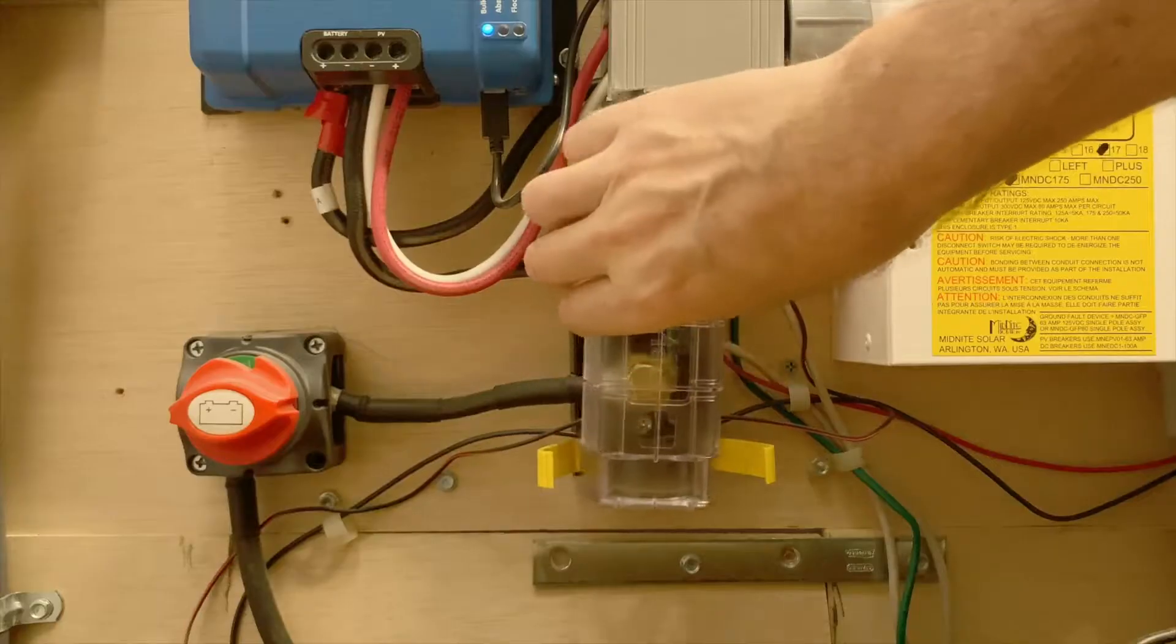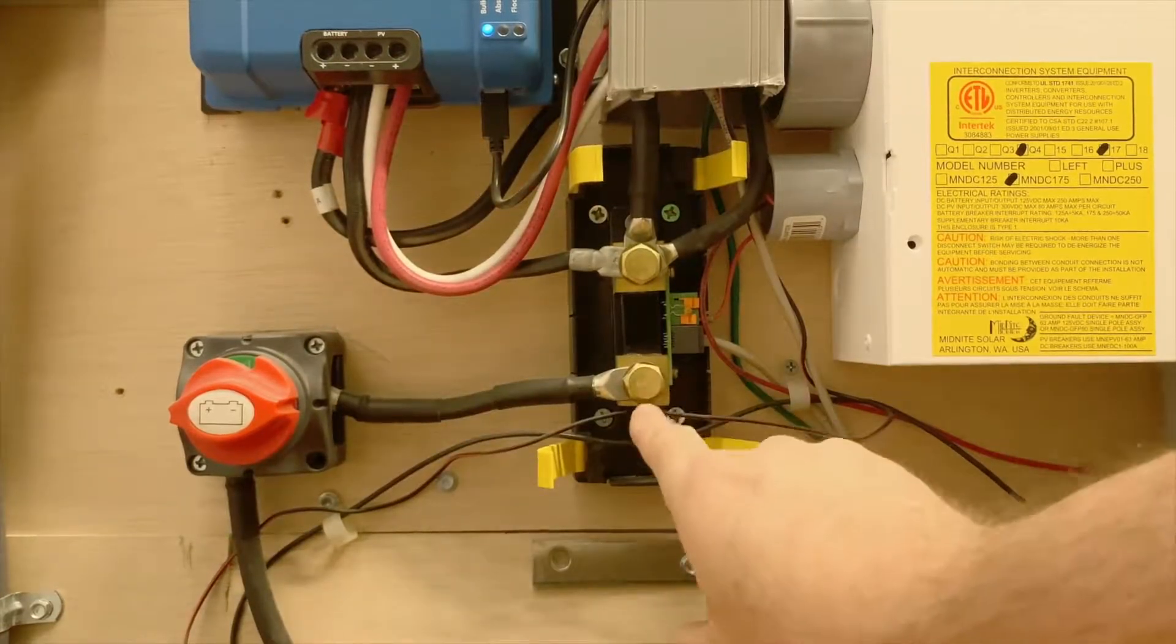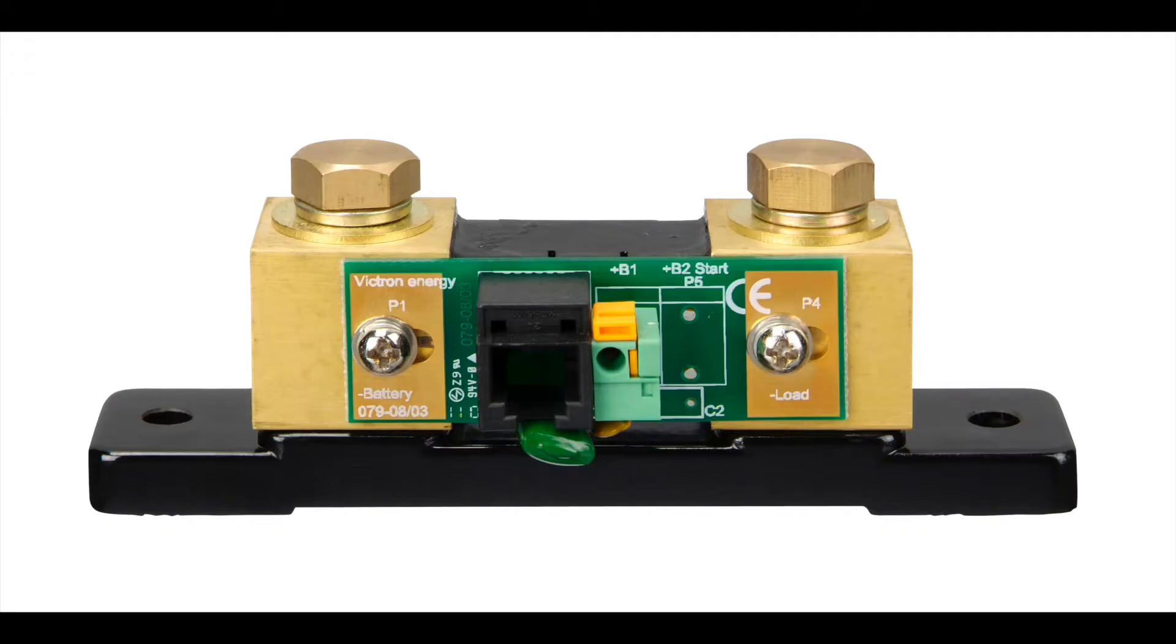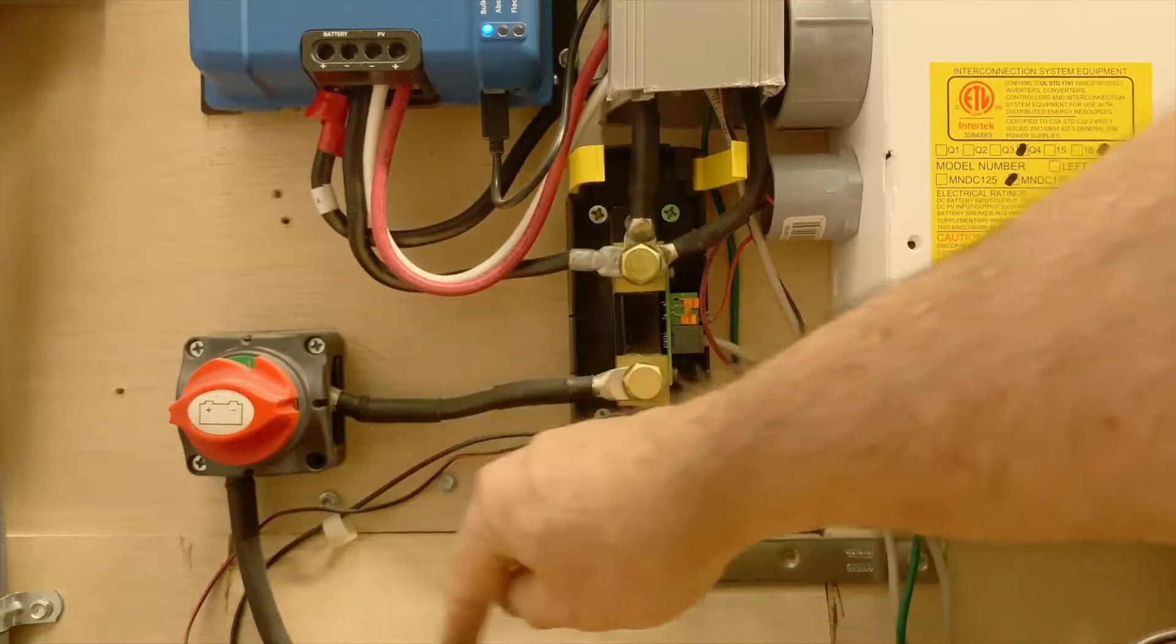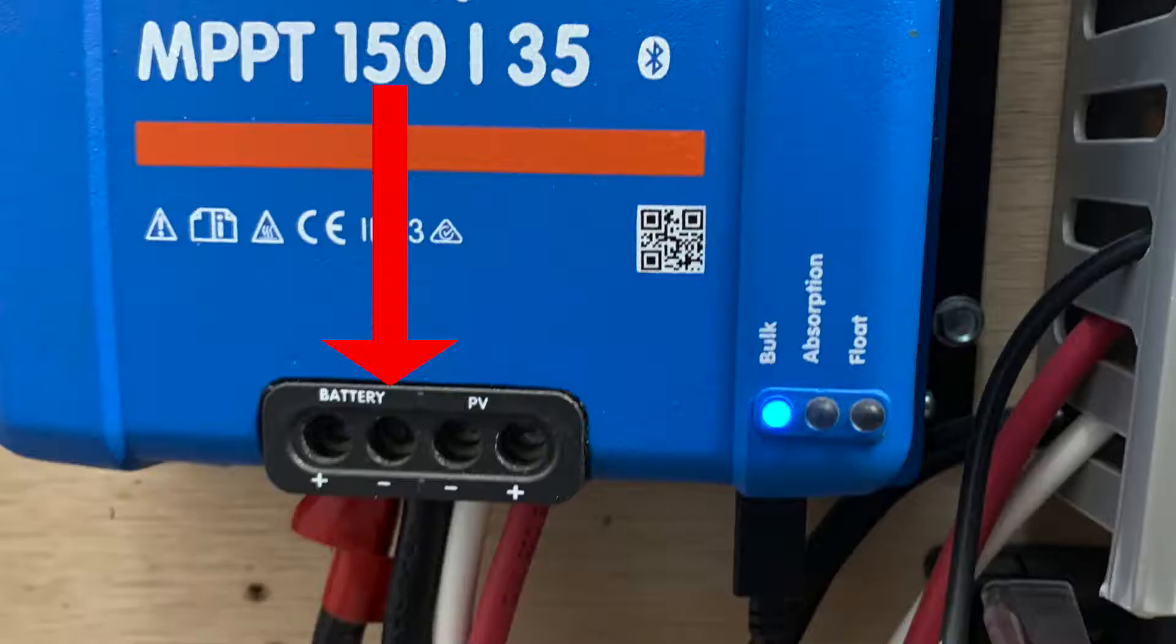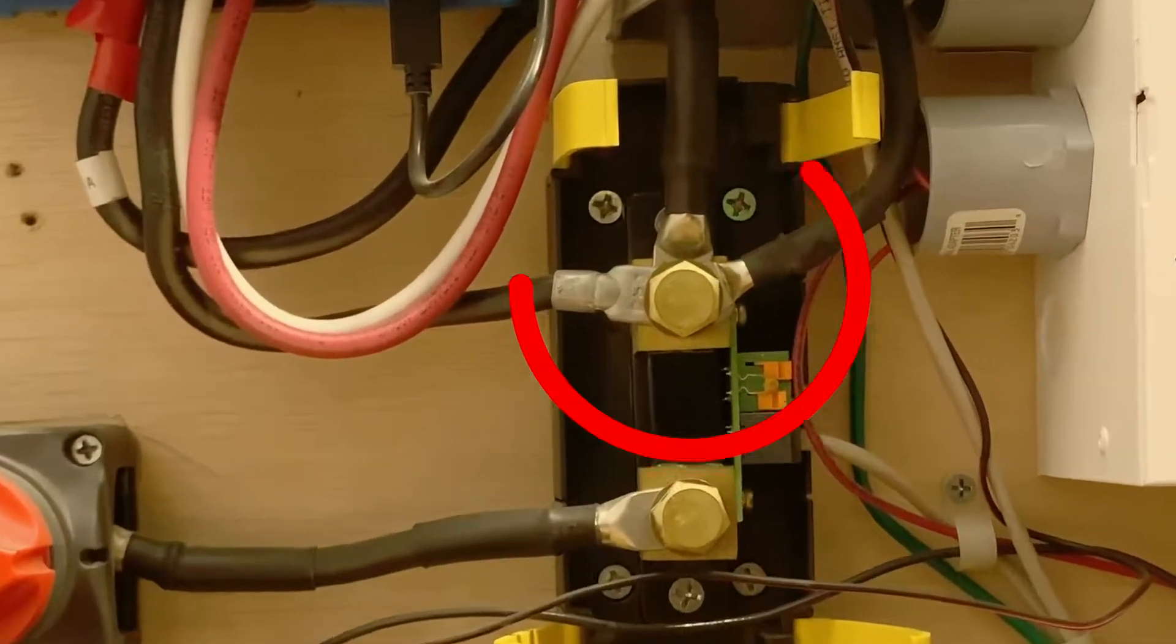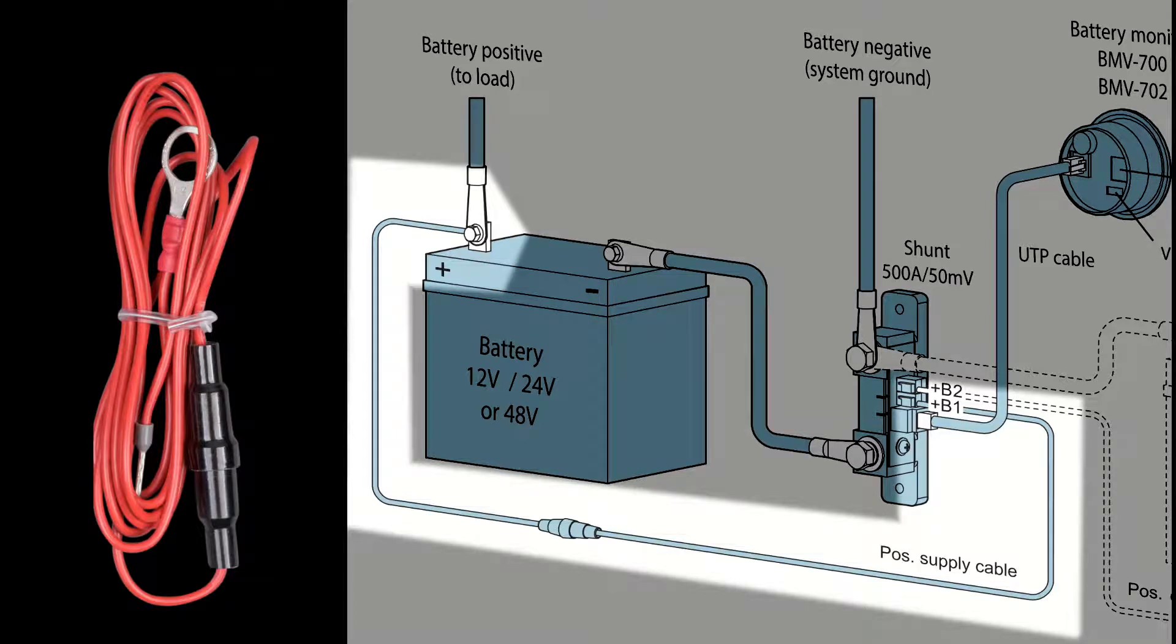The shunt is basically a big resistor that measures the current flow in and out of your battery. It's inserted across the negative side of your system between the negative post of the battery and all of the negatives of your equipment, such as your inverter, your chargers, and so forth. It's rated at 500 amps, and you can substitute a larger shunt if you need it. This post on the shunt connects to the negative post or bus bar of your battery system. I added a disconnect switch here, and the other post connects to the negative side of your inverter and all your solar chargers. This post can also hold several ring lugs and act as a bus bar.